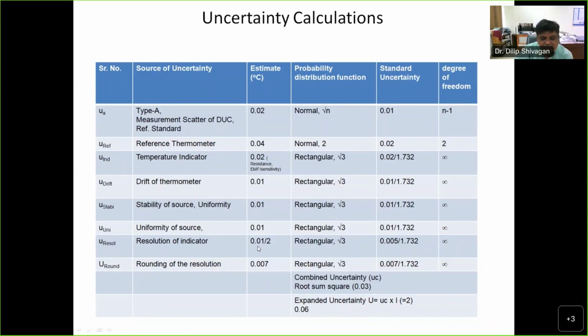Resolution, so it is d by 2. If it is a 0.01 degree thermometer, it is divided by 2 as the estimate, and then you put the rectangular distribution. Similarly, for rounding, if it is a 0.01 degree thermometer, logically it will round off anywhere from 0.05 to 0.09. At 0.1, definitely it will display 0.1. So there are 0.05, 0.06, 0.07, 0.08 and 0.09. So the average becomes 0.007. This is the logic behind choosing the rounding of our parameters.